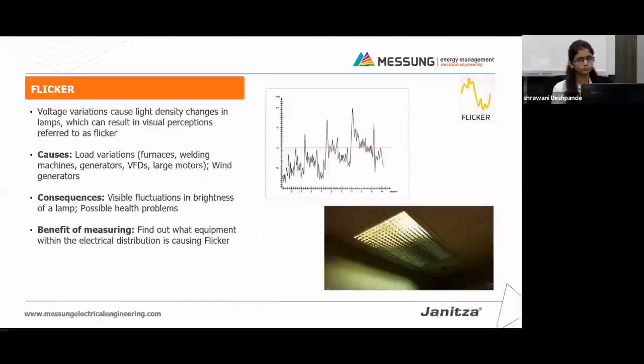The main thing is that these LED lights should be of good quality. They should have built-in low-pass filters which remove these high-frequency interferences. This EMI EMC can be up to 1 megahertz or 500 kilohertz or so. Only our UMG 512 or the 605 has the ability to measure the flicker, so there are very few energy meters which can measure it. This flicker isn't going to create much damage to equipment, but it's going to create more human damage, headaches and things like that.